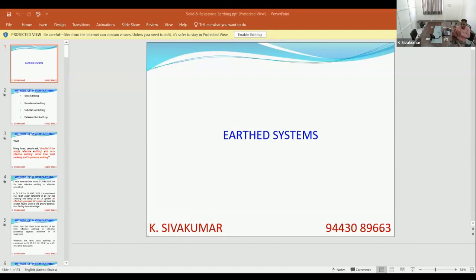So we say by derivation, if the zero sequence impedance is equal to positive sequence impedance, then the single phase to earth fault current is equal to 3-phase symmetrical short circuit current. People can refer to IS 13234. In that, it is clearly explained how to calculate the single phase to ground fault current.